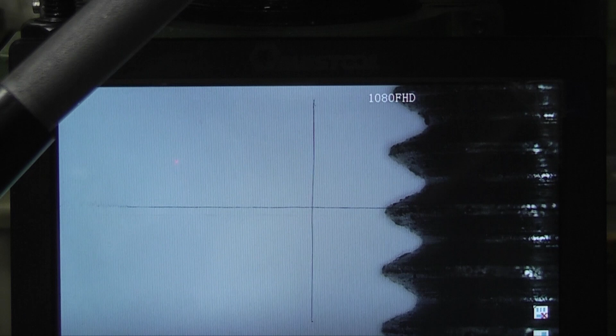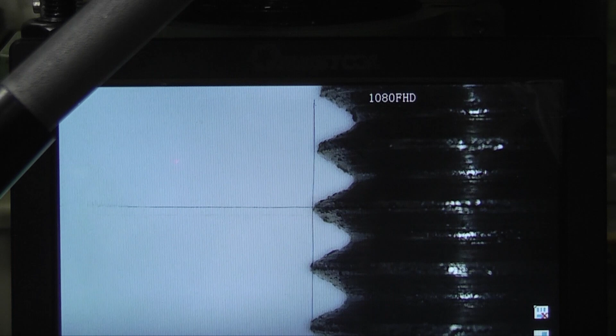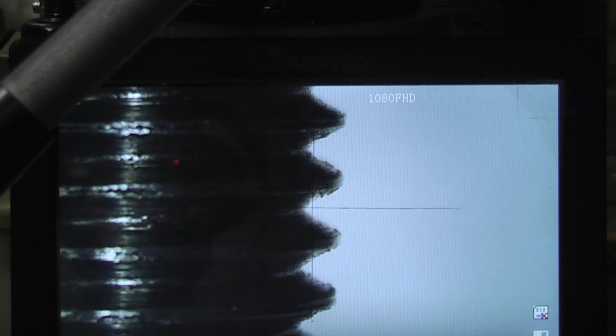Now I should be able to measure diameter. So bring the line up to the tip of the thread, which is about there. Set it to 0 and go across to the other side. I can move up and down to the tip of the next thread. About there, and that says that's 5.885 millimeter diameter. I'll move it so the crosshair is in the middle of the V.